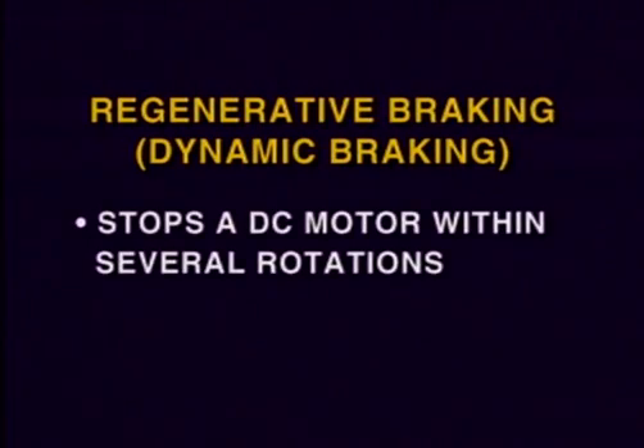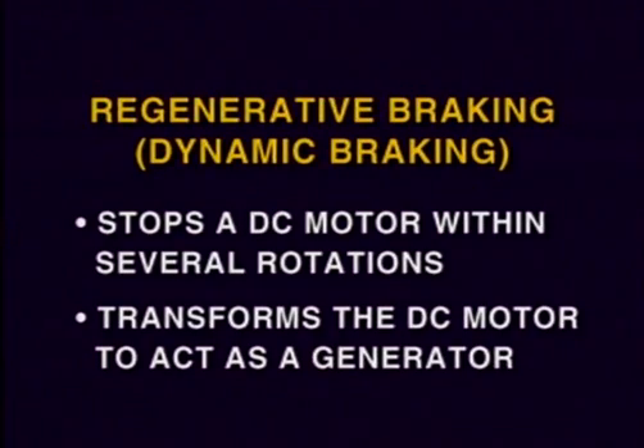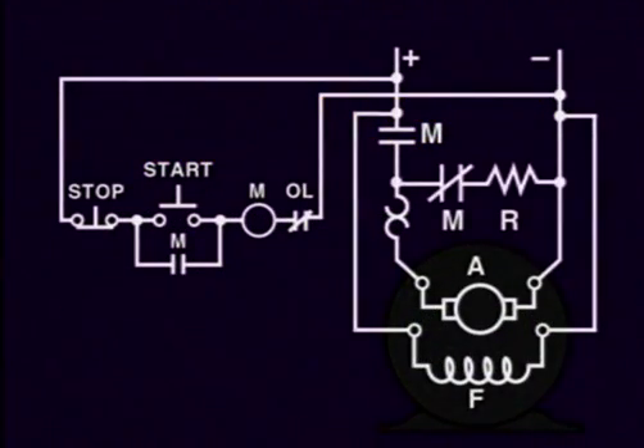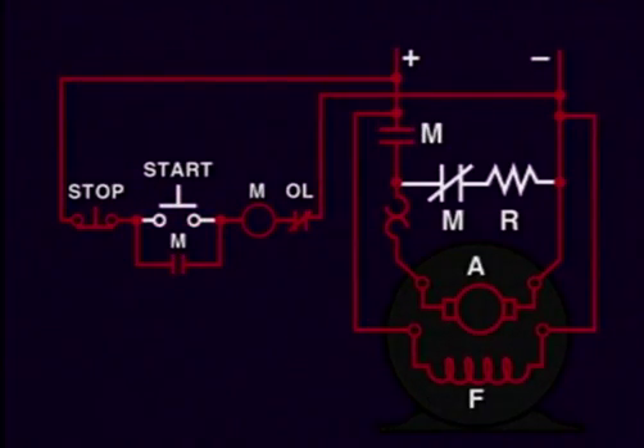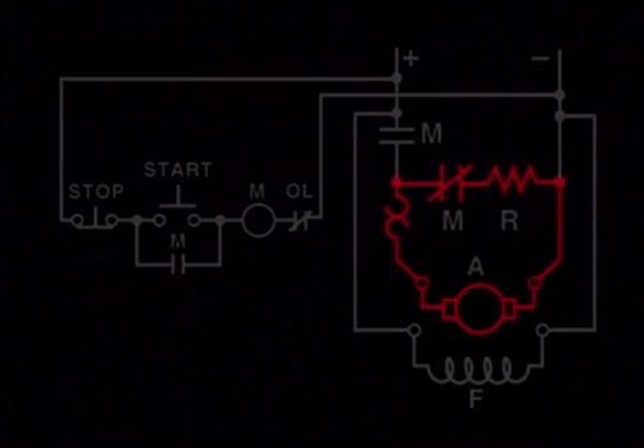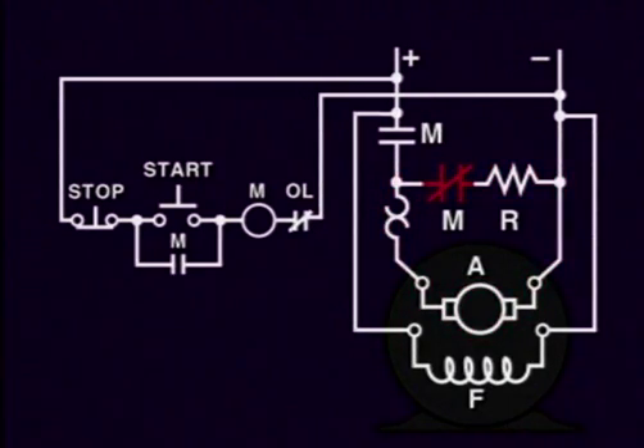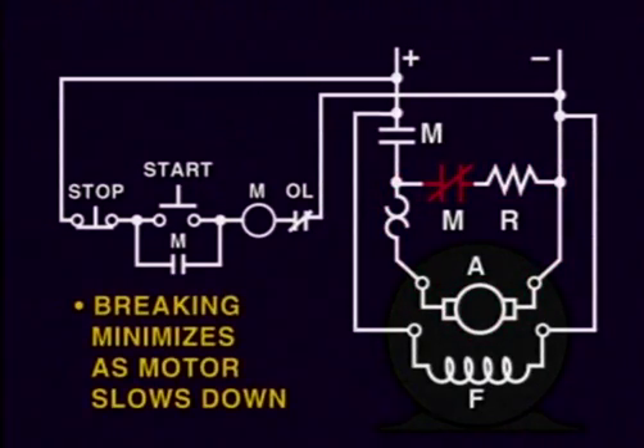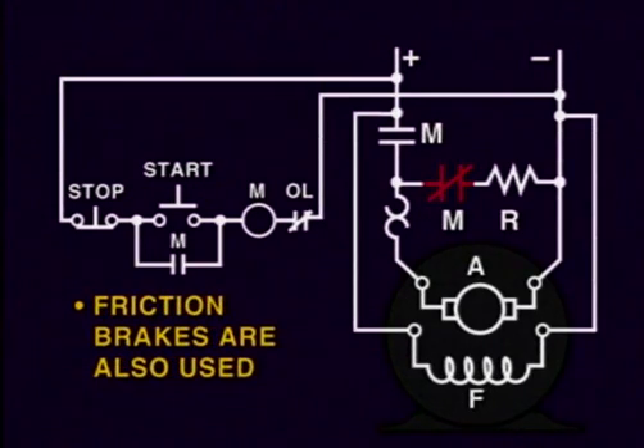Regenerative braking, also known as dynamic braking, is used with DC motors to bring them to a smooth stop within several rotations. This method uses, as a principle, the transformation of the motor to act as a generator. A small resistor is placed in parallel with the armature which, when turned off, will serve as a loaded generator that quickly stops the motor due to the reverse magnetic forces created. The braking action of this circuit minimizes as the speed of the motor decreases, and as a result, it cannot hold the load once the motor has stopped. Therefore, friction brakes are generally used along with regenerative braking to help bring the load to a complete stop and hold it stopped.